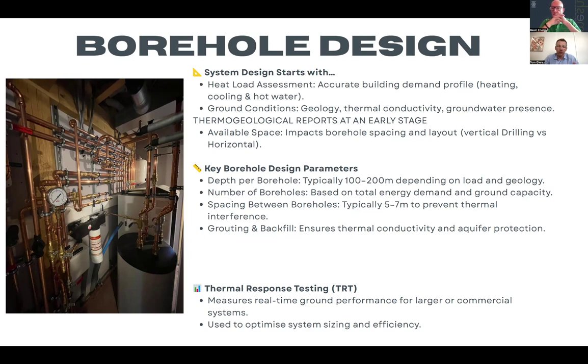So roughly, as a rule of thumb, but that depends on the geology, you are looking at one borehole at 100 meters for 5 kilowatt of heat output. If we're talking small domestic property, 12 to 15 kilowatts heat demand, the heat pumps are sized for the heat demand. With a domestic property with a boiler, you add heating demand and hot water demand on top, and that gives you the total demand for the boiler. With heat pump systems, you size the boreholes for the kilowatt heating demand of the heating system, and then of course you have to add the kilowatt demands throughout the year for the hot water, but that's just for the running hours of the system.